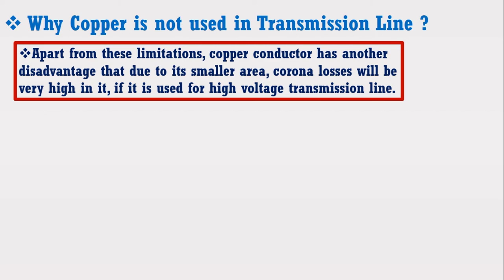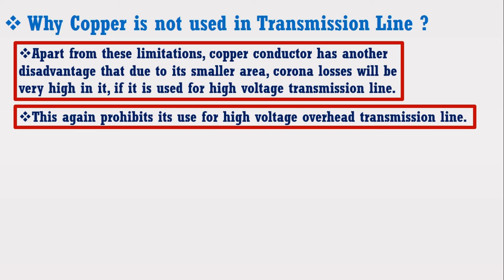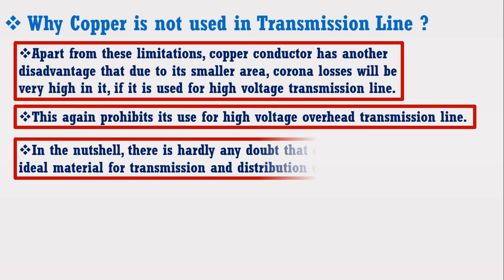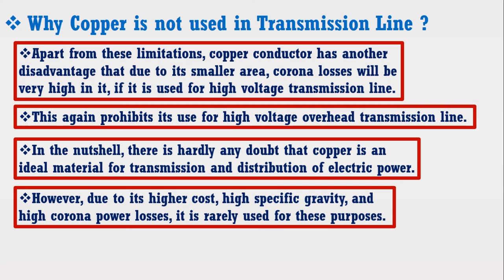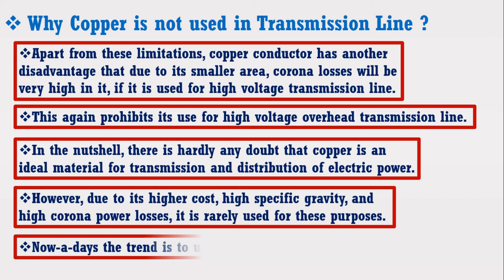Apart from these limitations, copper conductor has another disadvantage: due to its smaller cross-sectional area, corona losses will be very high if it is used for high voltage transmission lines. This again prohibits its use for high voltage overhead transmission lines. Therefore, in a nutshell, there is hardly any doubt that copper is an ideal material for the transmission and distribution of electrical power. However, due to its higher cost, higher specific gravity, and higher risk of corona power losses, it is rarely used for high voltage transmission lines.